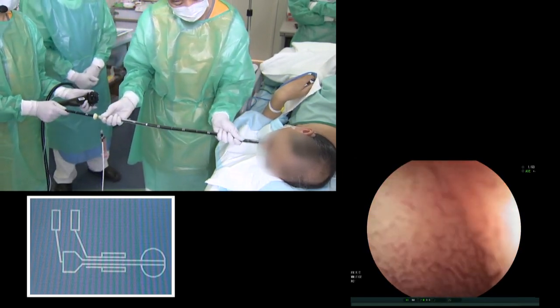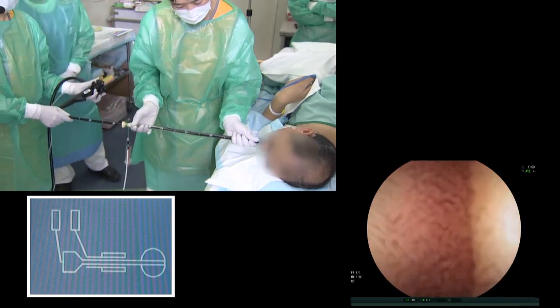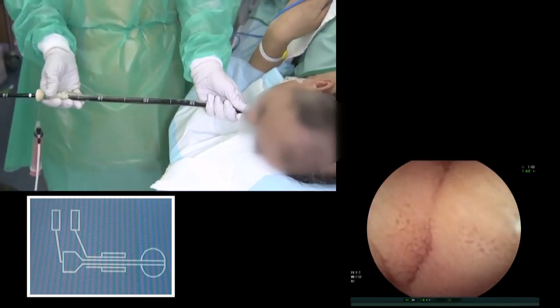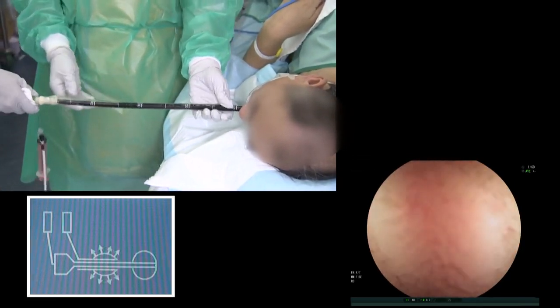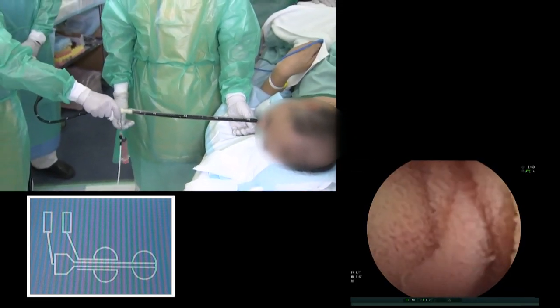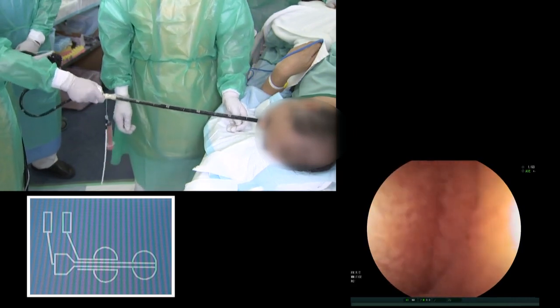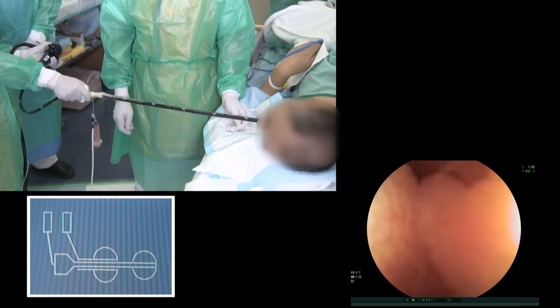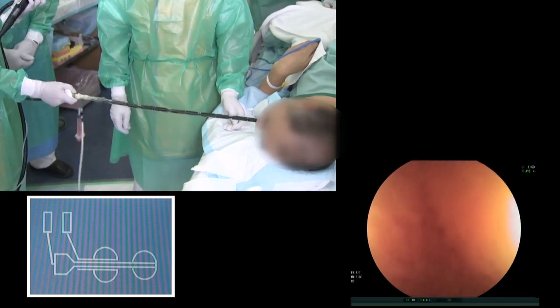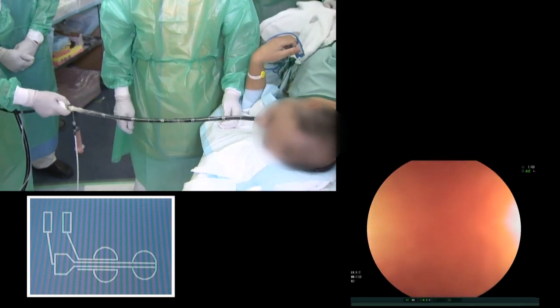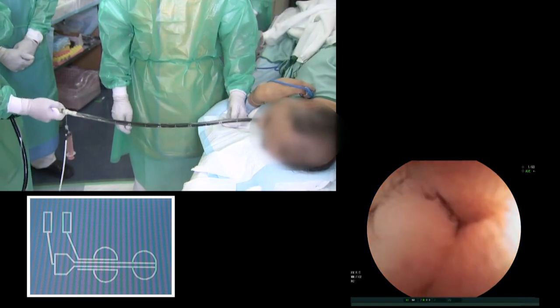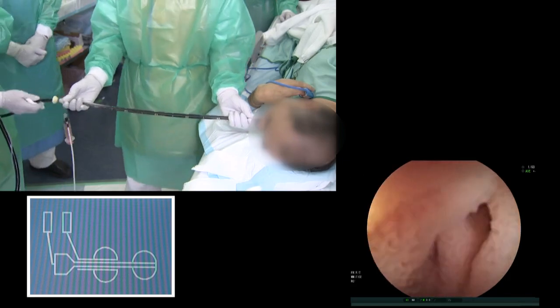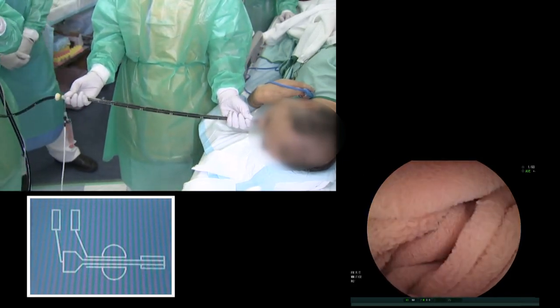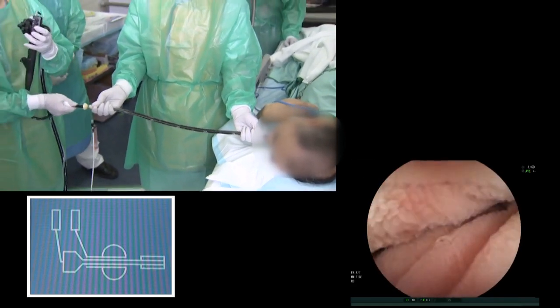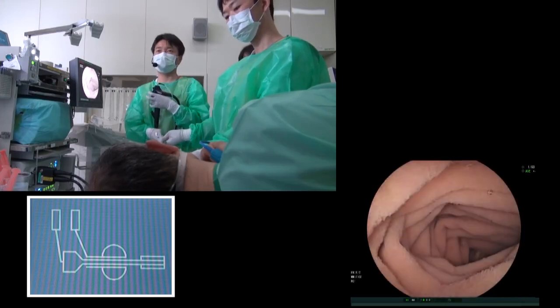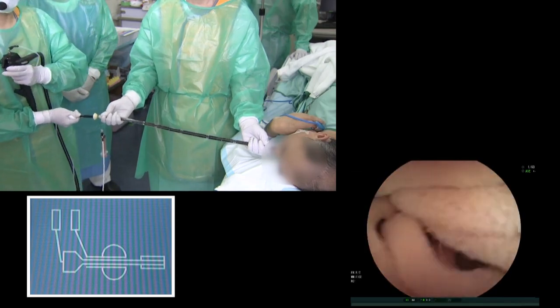When the endoscope shaft is advanced without the distal end moving forward, a complicated loop is formed and it will create a more disadvantageous situation for the next insertion step. In other words, by advancing the distal end of the endoscope without pushing the shaft too much, you can retain a simpler shape. When shortening without fluoroscopy, add some torquing movement to the left and right like this. When you see direct responses on the screen and you don't feel any resistance, you can assume that the endoscope is sufficiently shortened and unnecessary loops have been eliminated. During the shortening operation, it is important to arrange the shape as simply as possible to make the next step easier. I want to stress that you can't simply pull it. Ultimately, if the endoscope is straightened out and the lumen of the small intestine is visible, the next insertion will be easier.